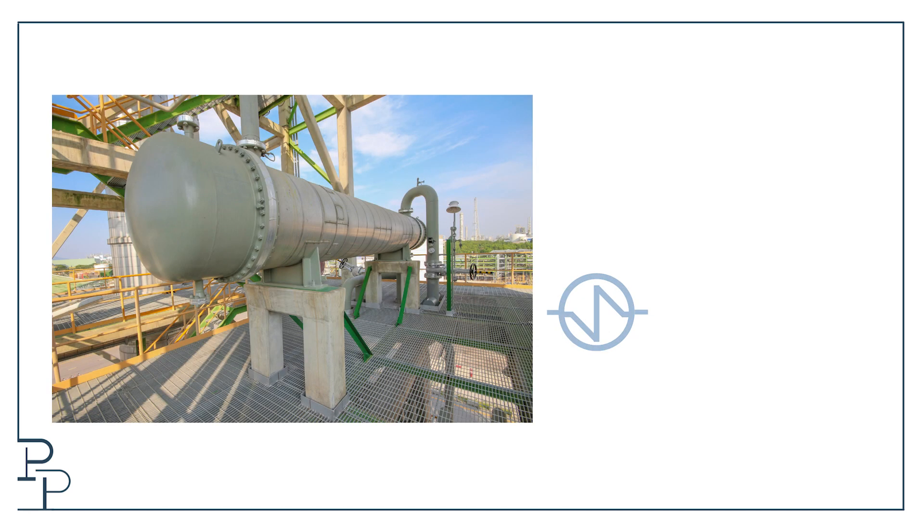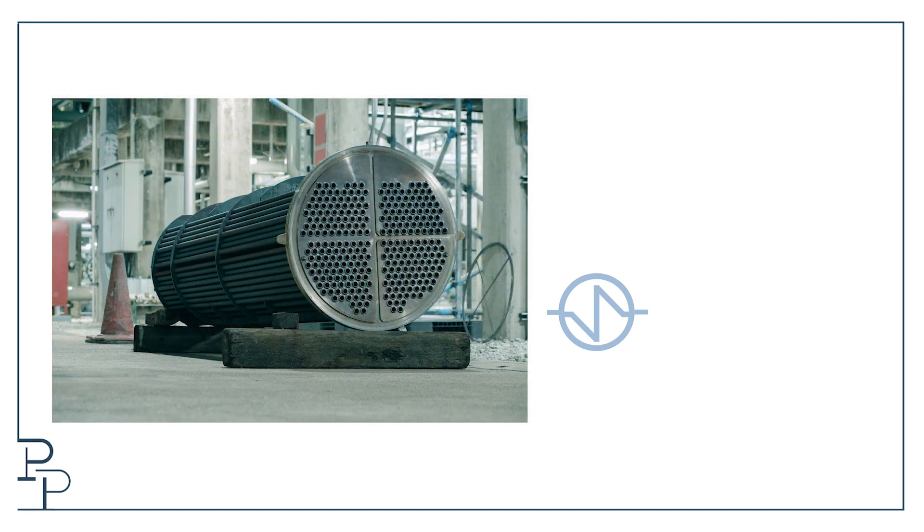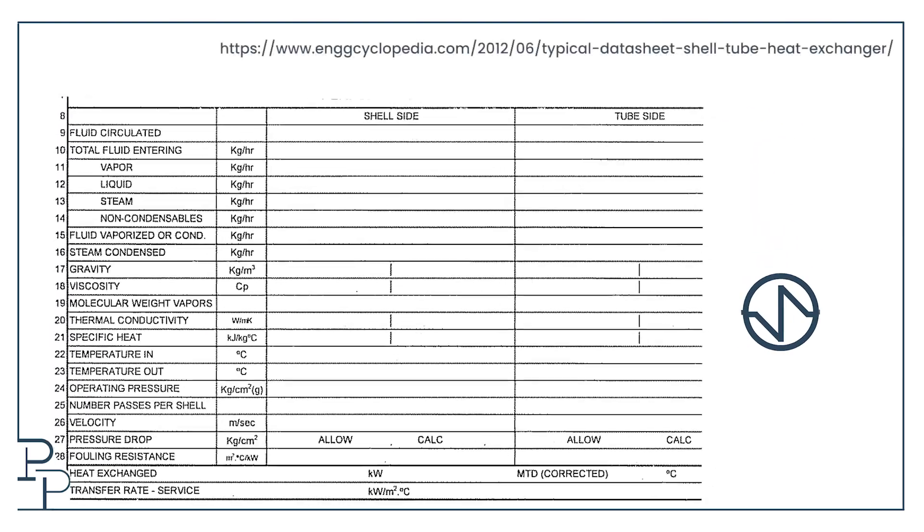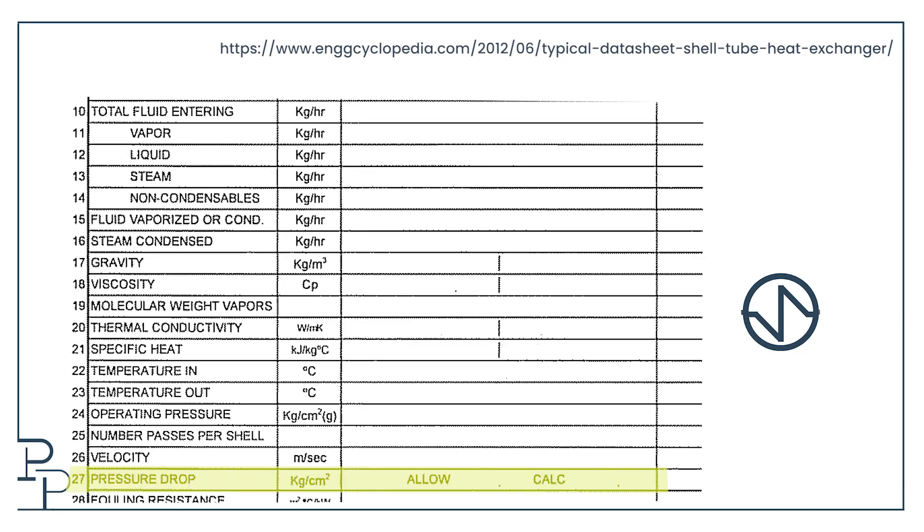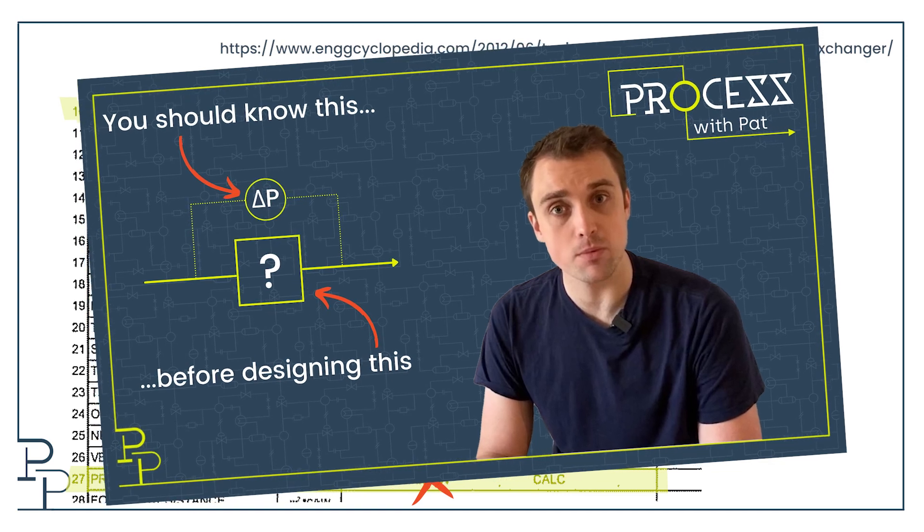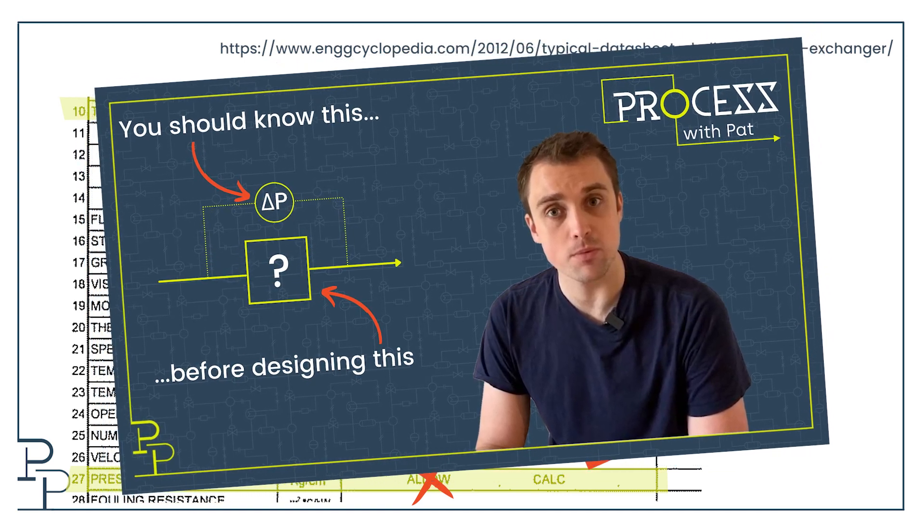Finally we need to know something about the heat exchanger. You could go and model it very rigorously, but if I'm faced with this kind of problem in my day-to-day work, this is how I'd approach it. I'd go look at the data sheet of the heat exchanger and see what is the calculated design pressure drop at the design flow rate. If you want to understand why you use the calculated and not the allowable pressure drop, you should go see my video explaining why you should actually know equipment pressure drop before you design it.